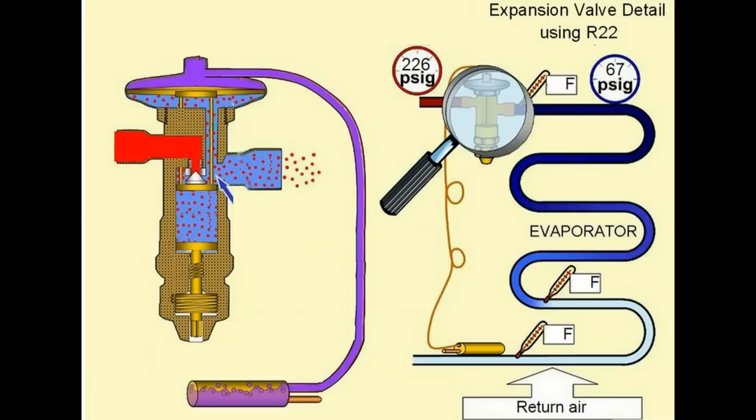So the first thing we're going to do in the first video is talk about just two of those forces. That would be the opening force which is the bulb pressure right here and the closing force which is the suction line pressure represented by the blue with the red dots here.